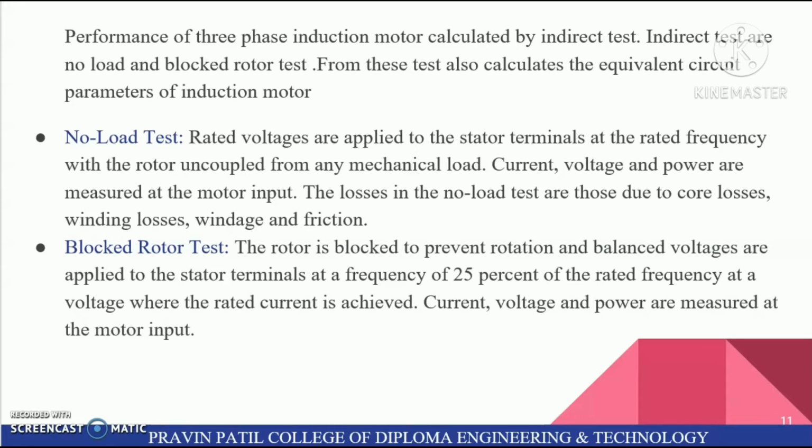Block rotor test. The rotor is blocked to prevent rotation and balanced voltages are applied to the stator terminals at a frequency of 25% of the rated frequency, at a voltage where the rated current is achieved. Current, voltage and power are measured at the motor input.